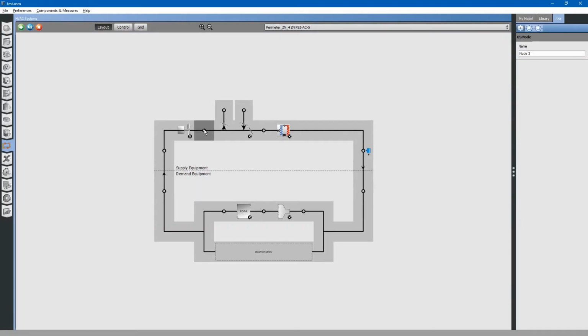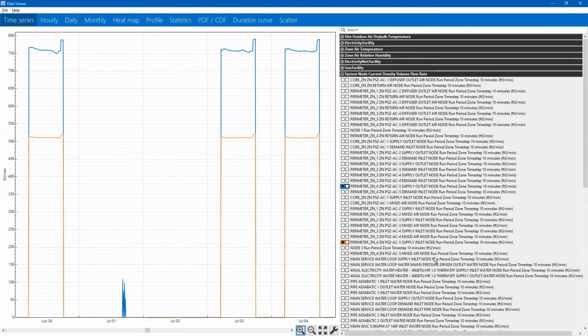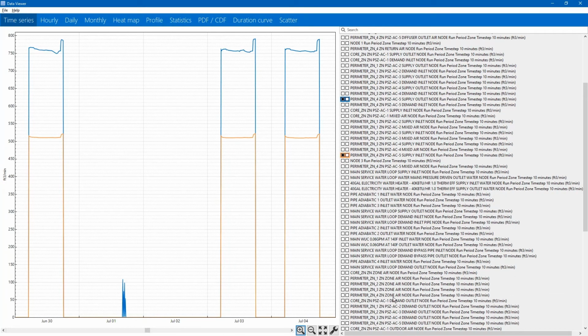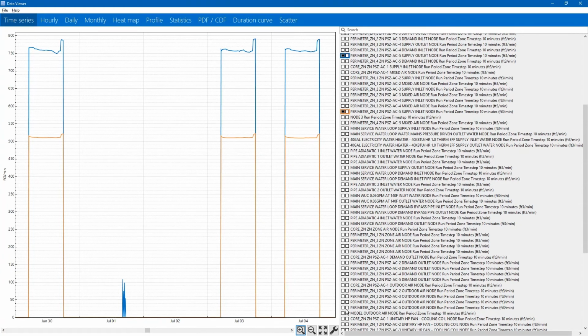And you can also check to see how the economizer dampers are operating. We can do relief air and outdoor air and mixed air. We would have to find these on here. Here's the outdoor air node. So the outdoor air is flowing a little over 250 CFM.